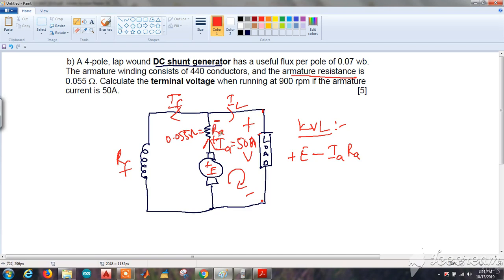Minus V equals zero. This completes the loop. I can write that E equals V plus Ia Ra. This is the equation for a shunt generator. We know Ra, we know Ia, we have to find the terminal voltage V. We don't know E, the generated EMF, but we can find it out.